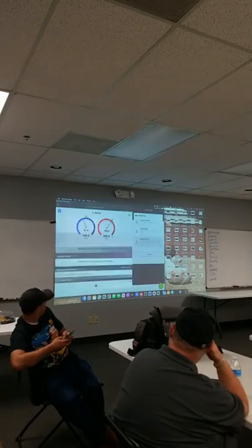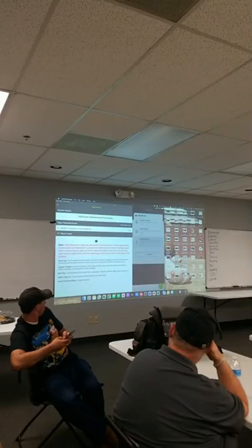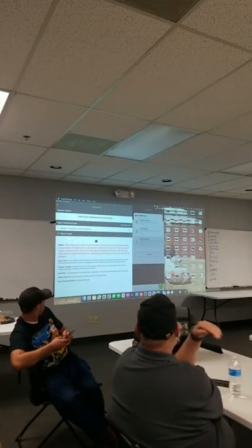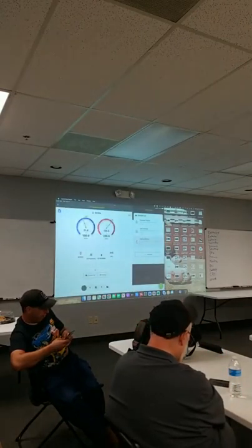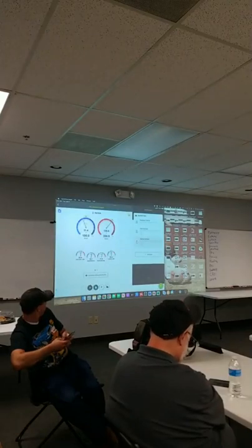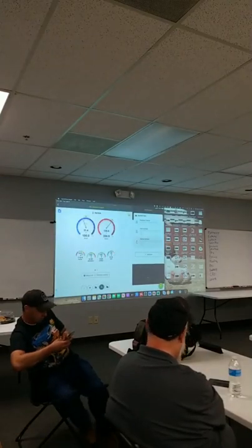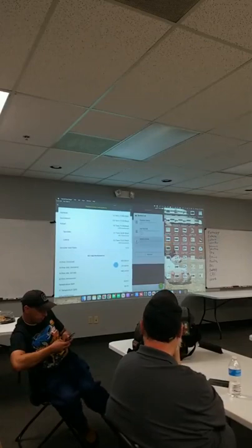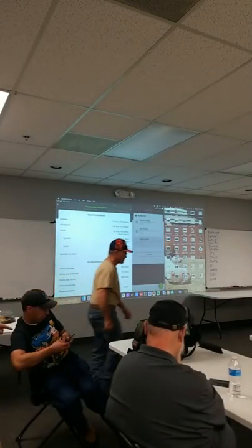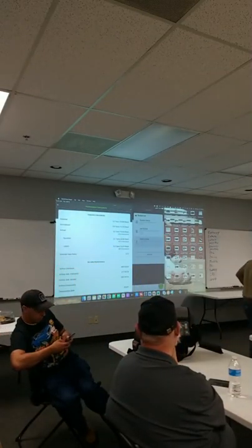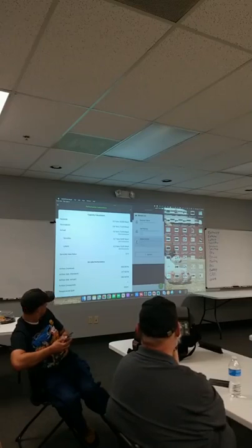My low side should drop to 100. And this right now is telling us the evaporator coil is going to be making ice, right? So any faults that he sees, we can see: subcooling, superheat readings, performance of the system. Everything I'm looking at here, I'm looking at Jimmy's phone in his hand, from my device. Right, so putting the data streaming and things like this up in the front end has made it a lot easier now to support your technicians in the field.